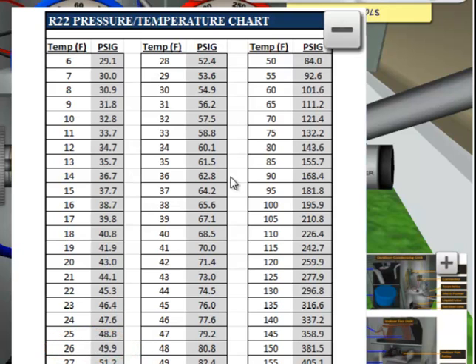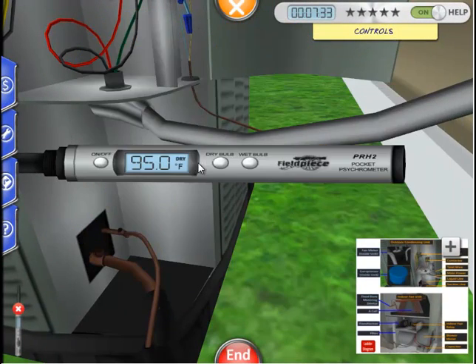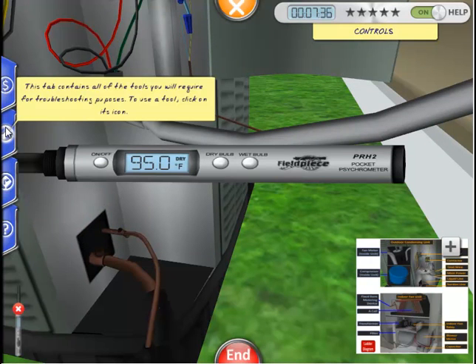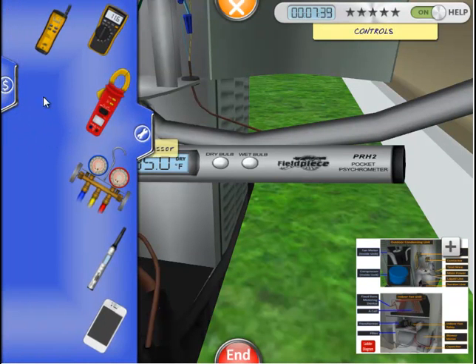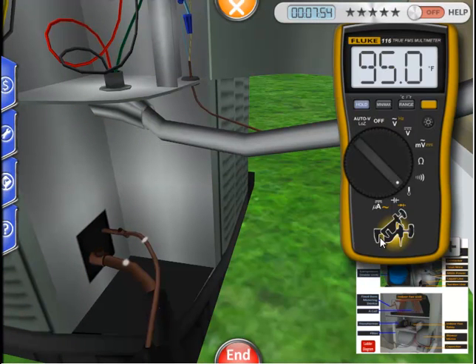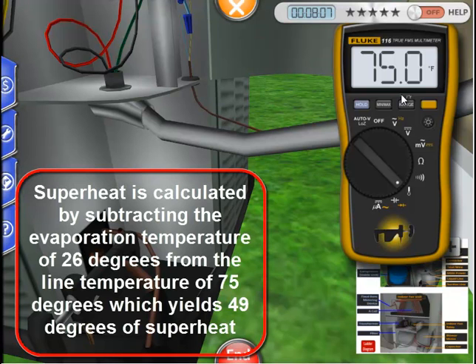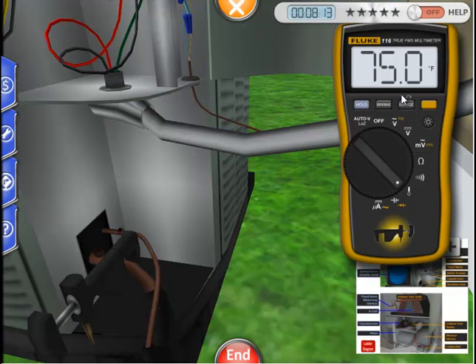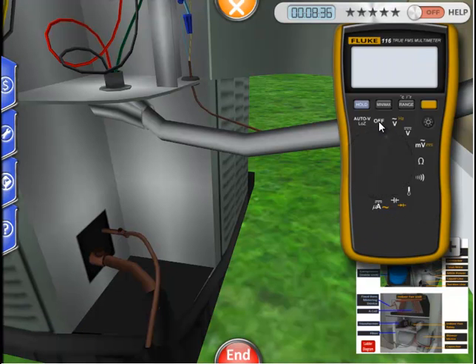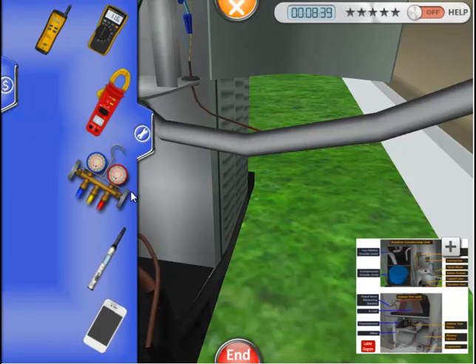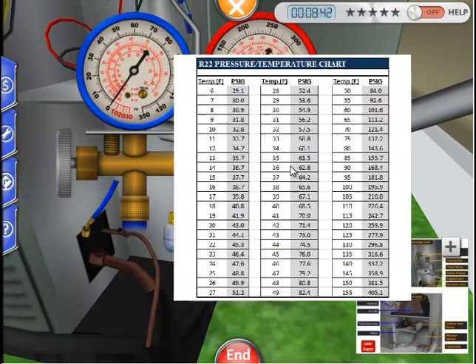We now need to calculate the actual temperature of the suction line using the clamp-on temperature probe feature of the multimeter. I'm going to select the multimeter out of the tool tab and move it to the temperature setting. Let's place the probe on the suction line. Our temperature reading is 75 degrees. We can now determine the superheat of the suction line, which is 75 degrees minus the evaporation temperature of 26 degrees, which yields 49 degrees of superheat. The superheat charging table will tell us whether this is an appropriate level of superheat for the given ambient conditions. The superheat table is available when the manifold gauge is displayed. To get the superheat table, just click on the pressure table.